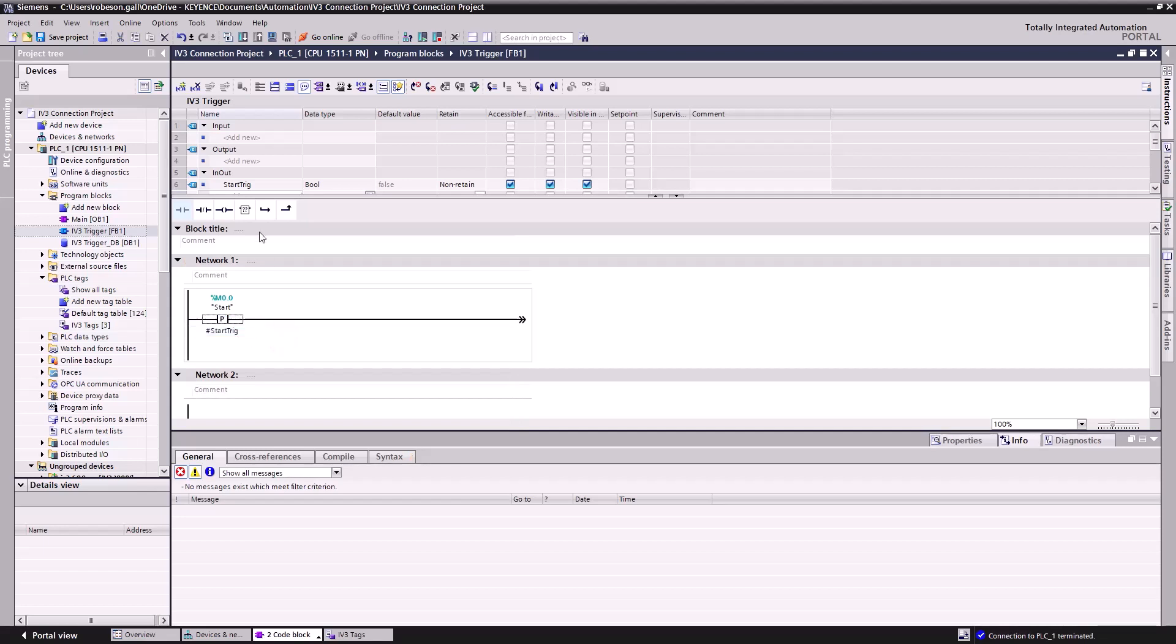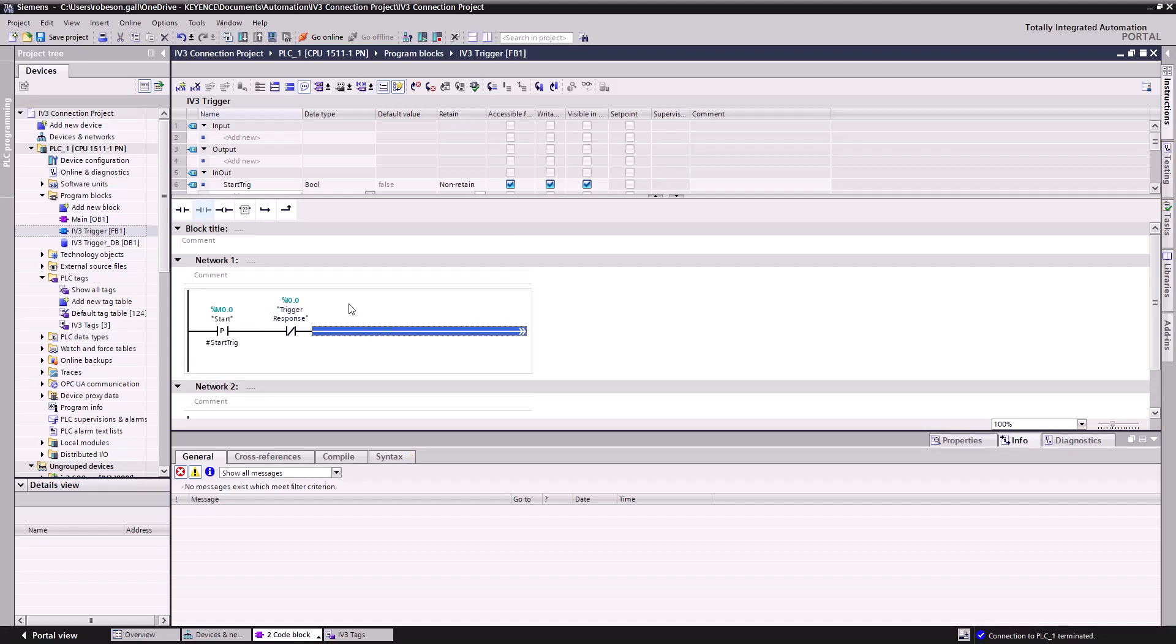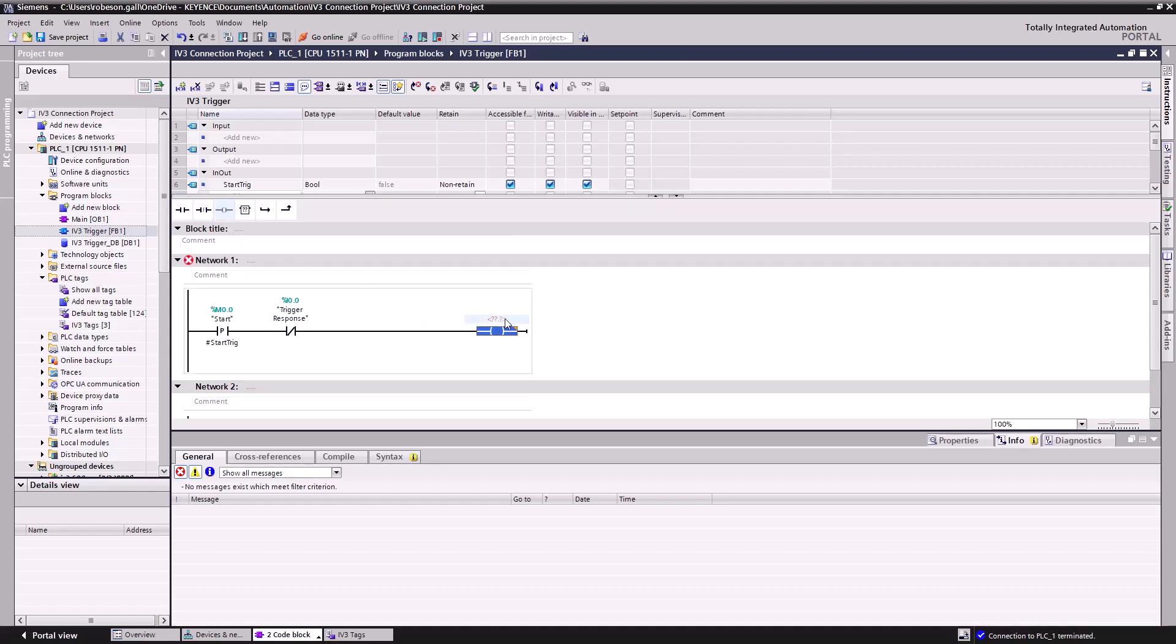Next, we'll drag a normally closed contact to the right. We'll assign this to our Trigger Response tag. This makes it so the PLC stops sending our trigger request once the IV-3 confirms it's received the request. Now we'll drag a coil to the right of the response, and we'll assign this to our Trigger Request tag.